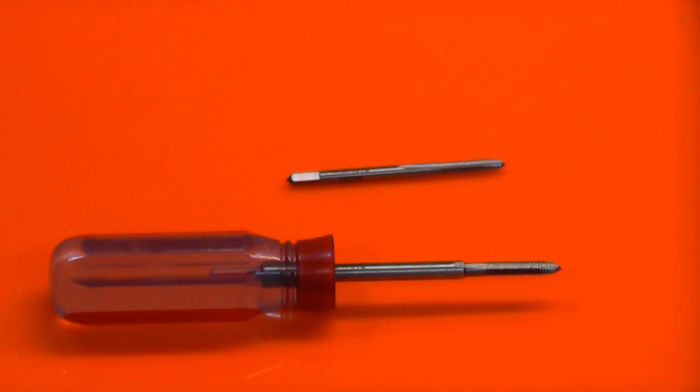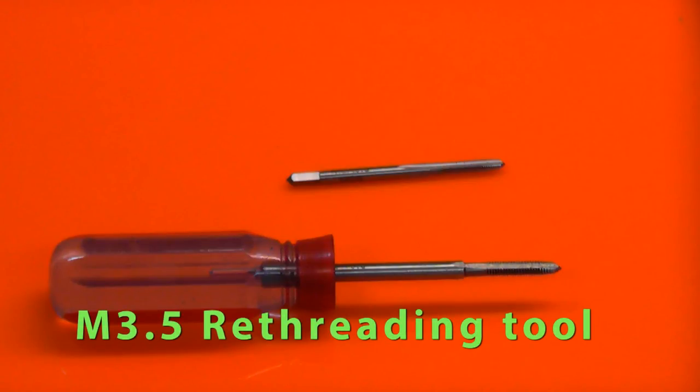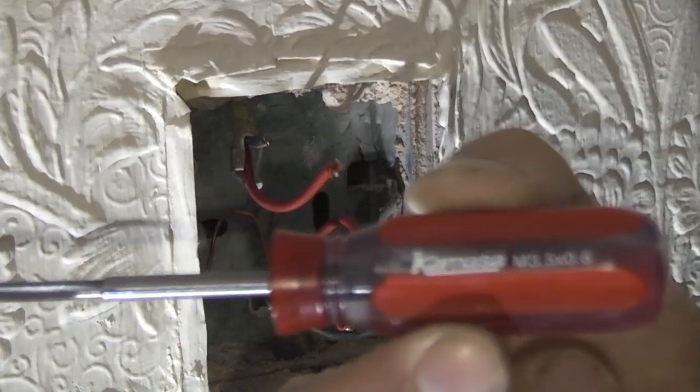When it comes to re-tapping the hole you can either use a tap wrench and an M3.5 tap if you're in the UK or you can buy a dedicated tool like this one which is specifically made for re-threading socket back boxes.